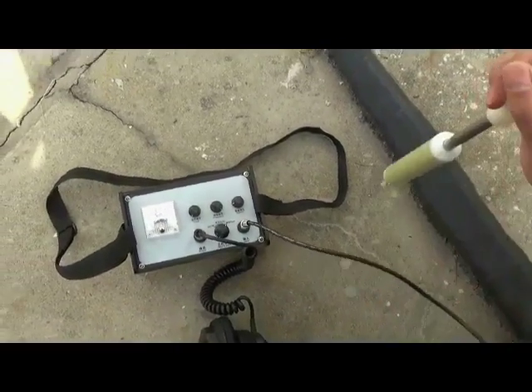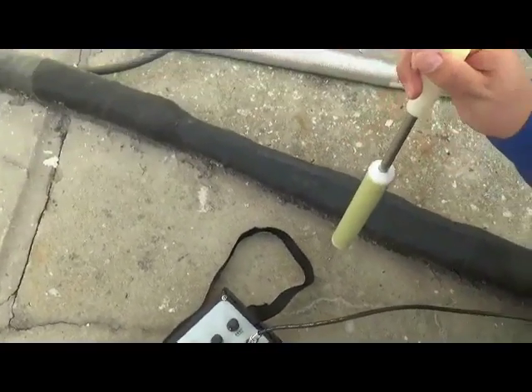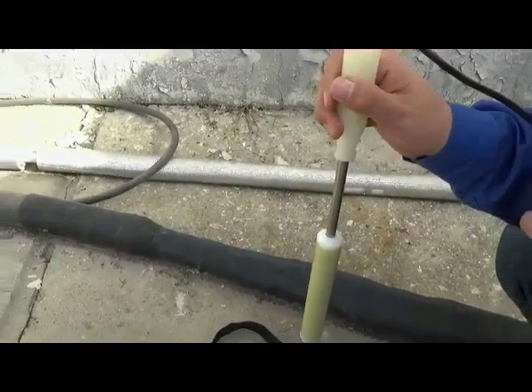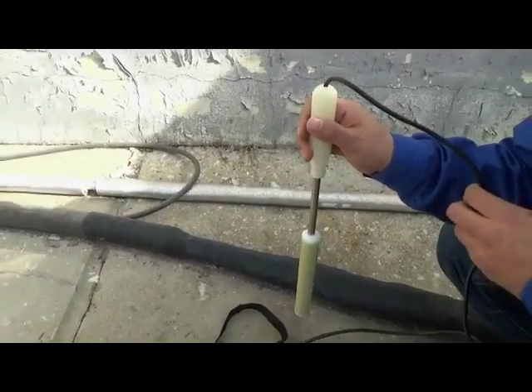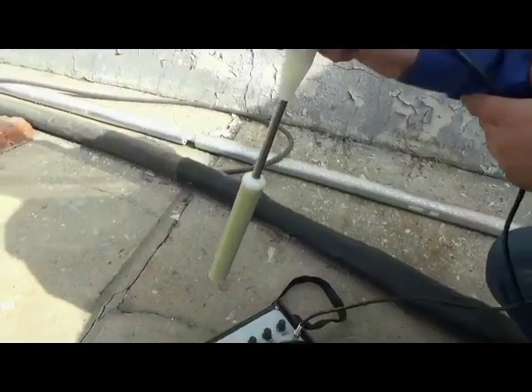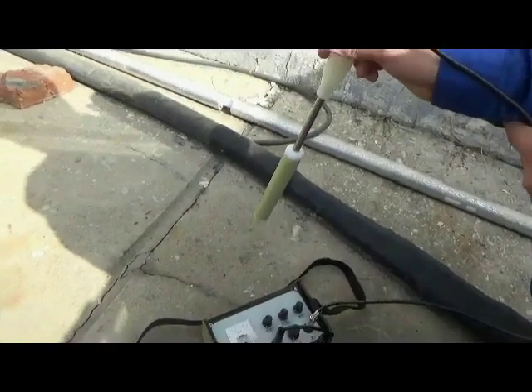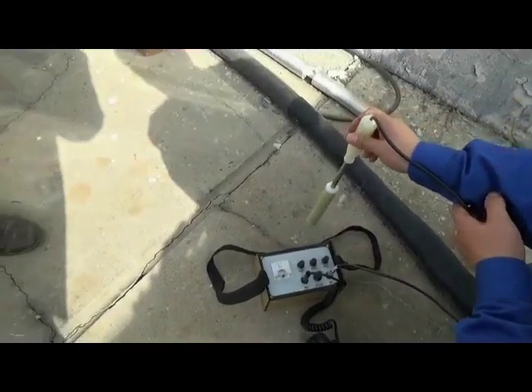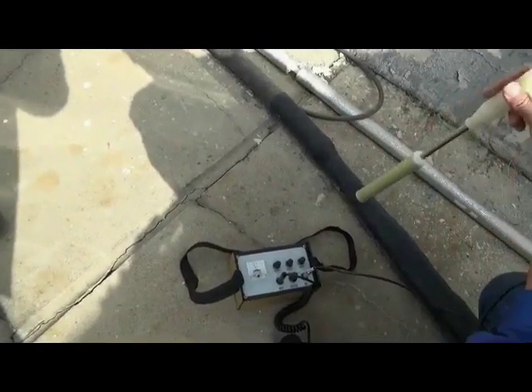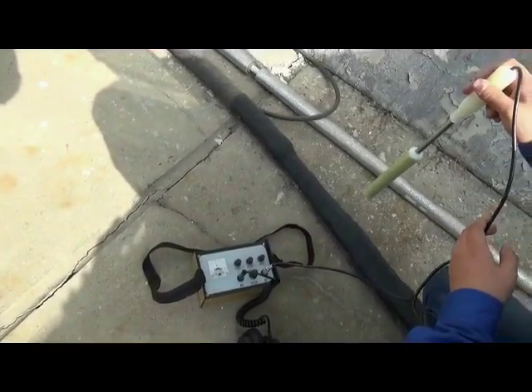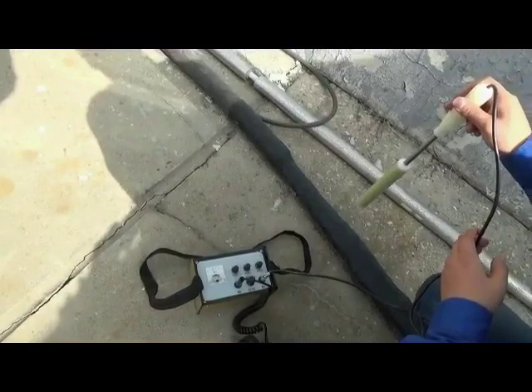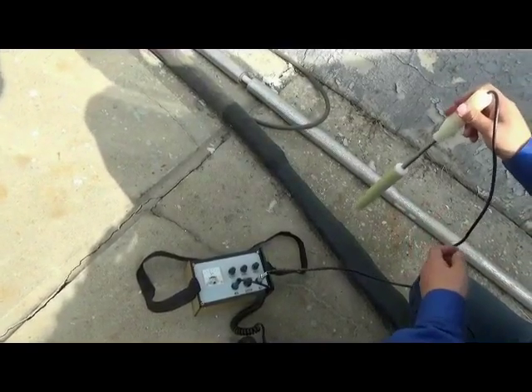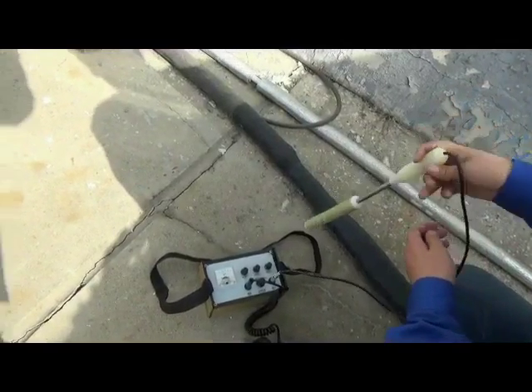There are two detecting methods. One is wave trough method. Keep detect rod vertically. The sound is the loudest on both sides of cable. The sound is minimum right above cable.